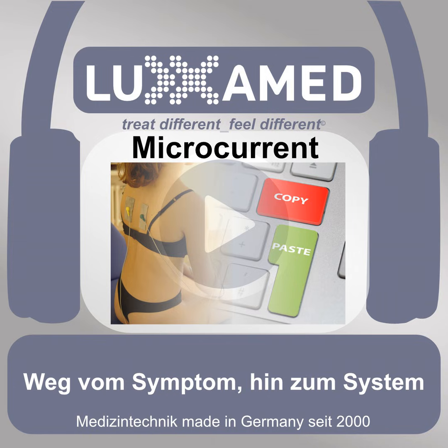A second practical point concerns the light channels. That is an important aspect. The light channels are assigned in our system. So we have 2 light channels, 4 microcurrent channels, so we have a fixed assignment here. Light channel 1 is assigned to our A channel, and light channel 2 is assigned to the C channel. That means the color in which a light head shines also indirectly gives you information about how the polarity of the channel is currently assigned, which in practice can of course be a useful and small feedback signal when you are working in the automatic range and need a quick visual reference point without having to look at the display specifically.